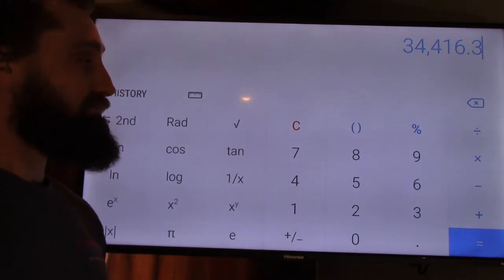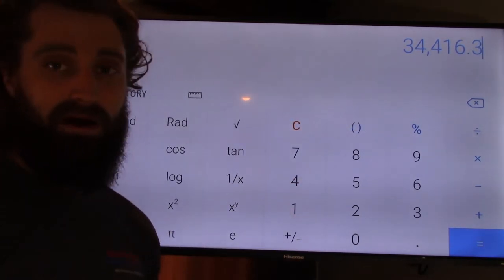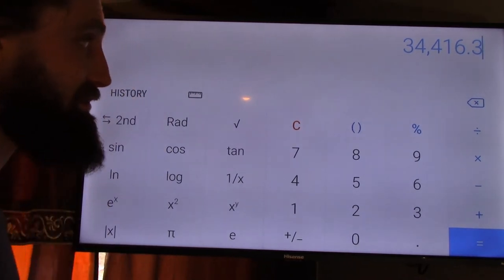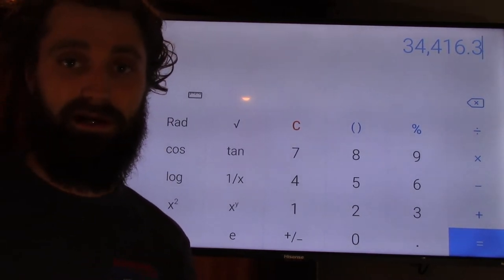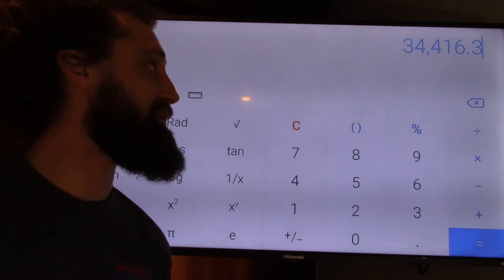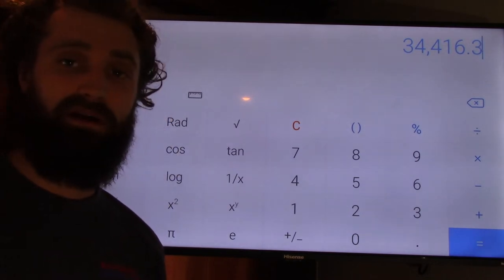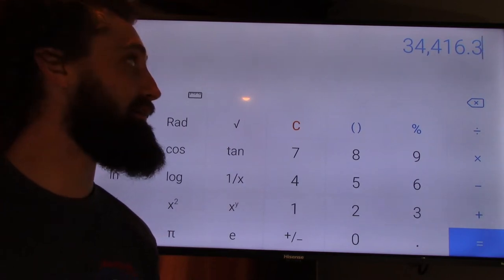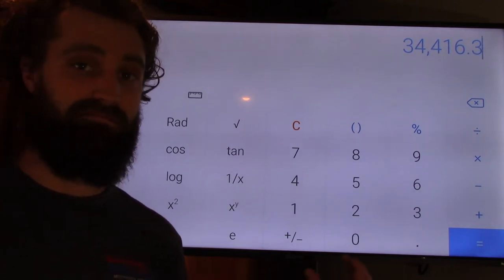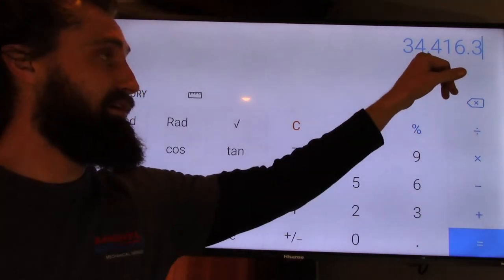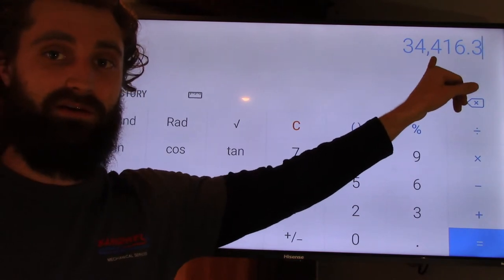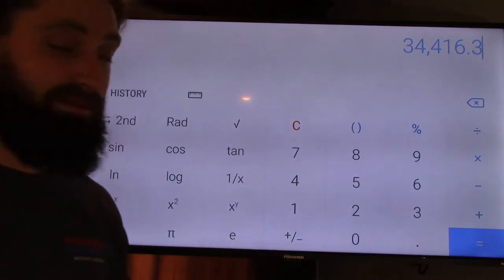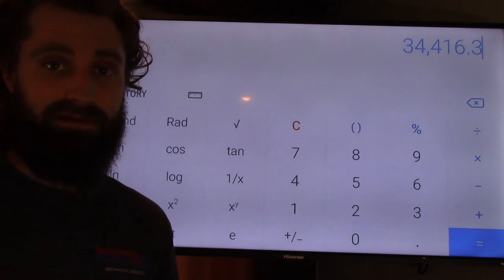So, 34,000 BTU. Honestly, if I went to Mrs. Complainer Lady and said, this is what I measured, it is 94 degrees outside today, and it's the middle of August, the sun's beating on your condenser, it's rated at 36, and we're getting 34.4. That's not bad.